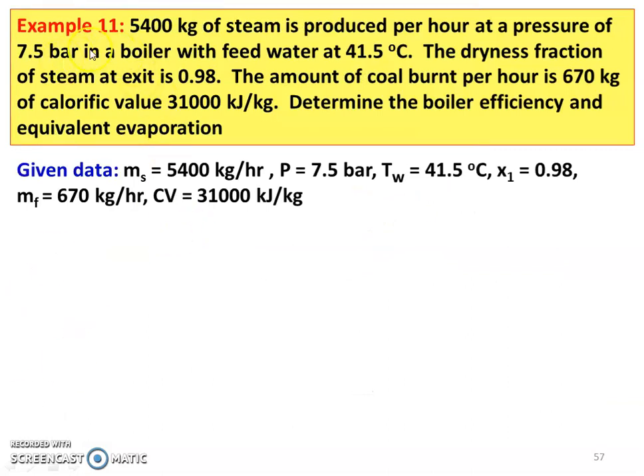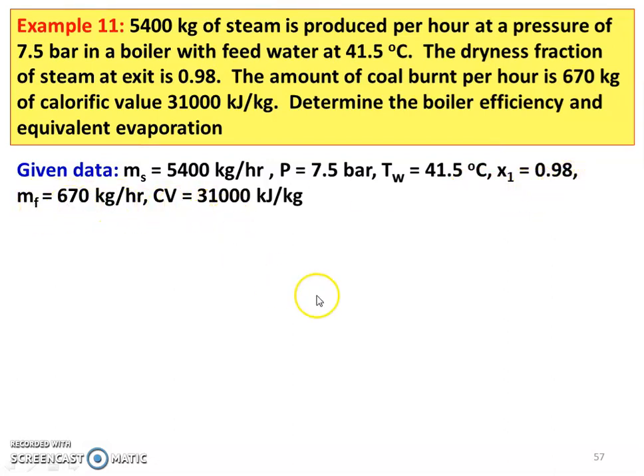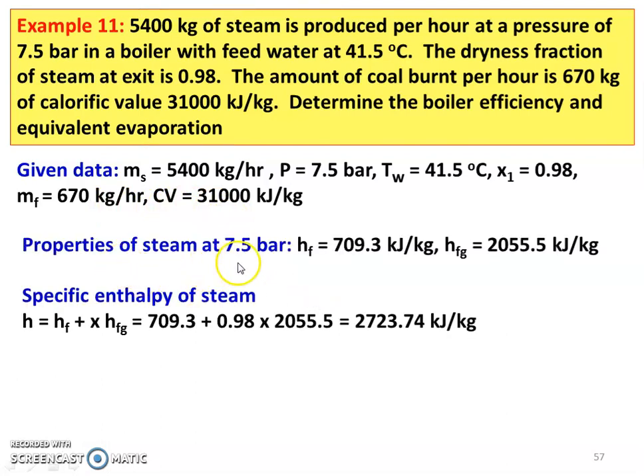The next question: 5,400 kg of steam is produced per hour at a pressure of 7.5 bar in a boiler, with feed water at 41.5 degrees Celsius. The dryness fraction of the steam at exit is 0.98. The amount of coal burnt per hour is 670 kg and the calorific value is 31,000 kJ per kg. Determine boiler efficiency and equivalent evaporation. Given data: mass of steam produced 5,400 kg per hour, pressure 7.5 bar, water temperature 41.5 degrees Celsius, dryness fraction 0.98, mass of fuel 670 kg per hour, calorific value 31,000 kJ per kg. Properties of steam at 7.5 bar: hF equals 709.3 kJ per kg, hFG equals 2055.5 kJ per kg.